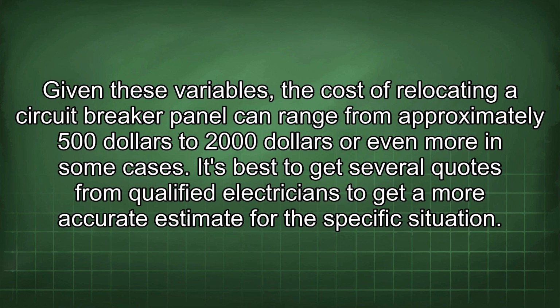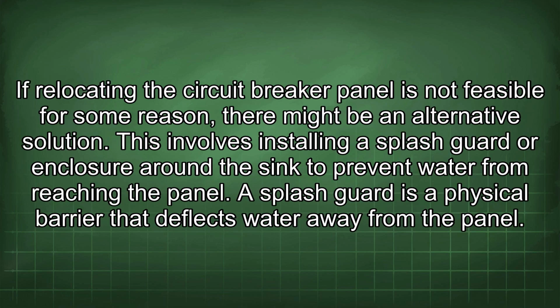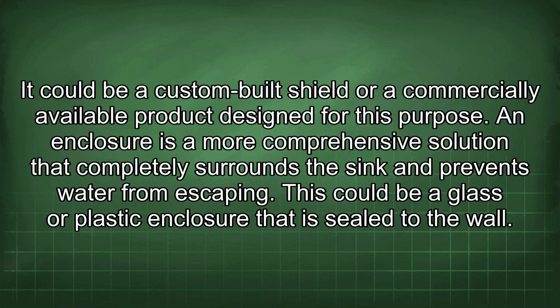If relocating the circuit breaker panel is not feasible for some reason, there might be an alternative solution. This involves installing a splash guard or enclosure around the sink to prevent water from reaching the panel. A splash guard is a physical barrier that deflects water away from the panel. It could be a custom-built shield or a commercially available product designed for this purpose. An enclosure is a more comprehensive solution that completely surrounds the sink and prevents water from escaping. This could be a glass or plastic enclosure that is sealed to the wall.